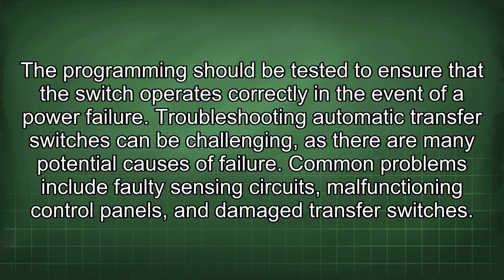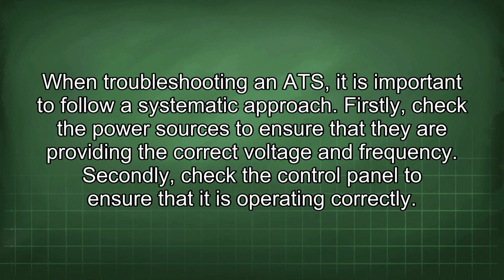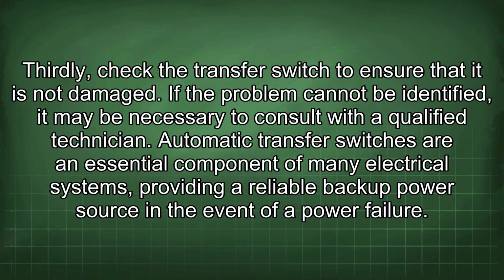Troubleshooting automatic transfer switches can be challenging, as there are many potential causes of failure. Common problems include faulty sensing circuits, malfunctioning control panels, and damaged transfer switches. When troubleshooting an ATS, it is important to follow a systematic approach. Firstly, check the power sources to ensure that they are providing the correct voltage and frequency. Secondly, check the control panel to ensure that it is operating correctly. Thirdly, check the transfer switch to ensure that it is not damaged. If the problem cannot be identified, it may be necessary to consult with a qualified technician.